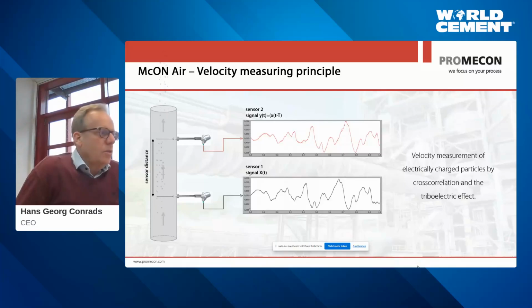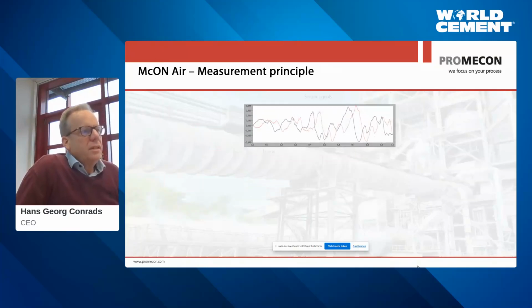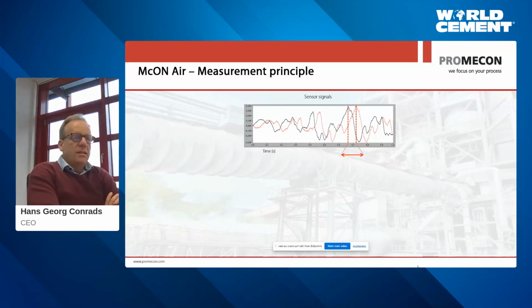Now there's a second sensor which is downstream, which in this picture is called sensor 2. And this sensor 2 basically picks up a very similar time signature. The reason for that is simply that the flow pattern between sensor 1 and sensor 2 will not change dramatically. It will pretty much be the same as on sensor 1. It will be very similar. So if you take these two time signatures and match and overlap them, you will see they are very similar. You can see it with your bare eyes. But of course, you can also see they're time shifted because the sensors do not sit at the same location. One sensor sits upstream, the other sensor sits downstream. And therefore, you can definitely see a time shift between the signals.